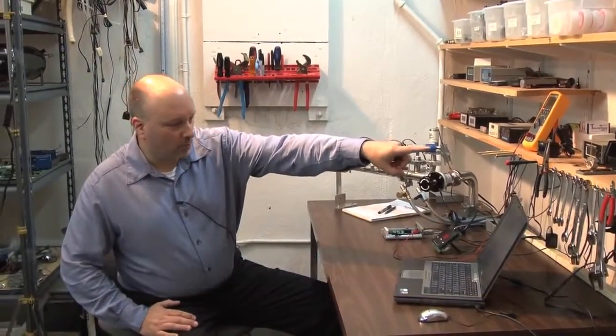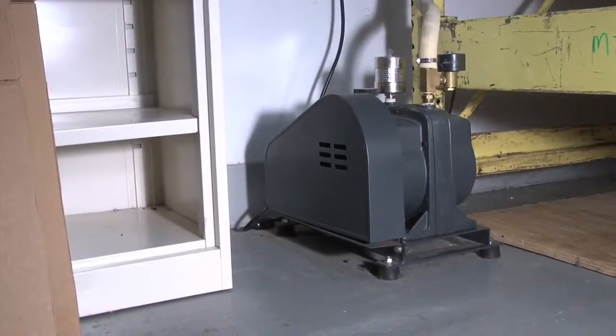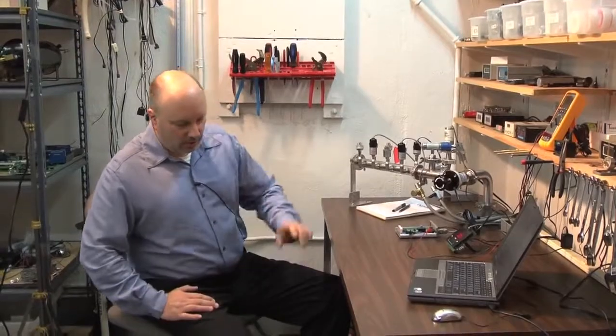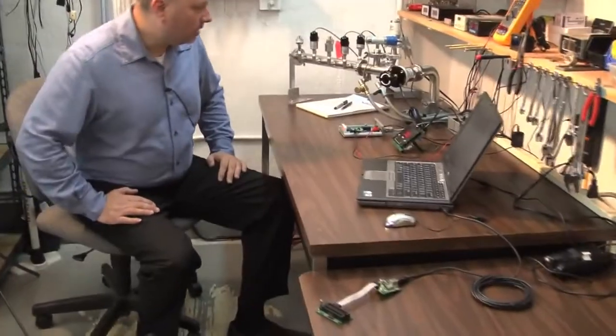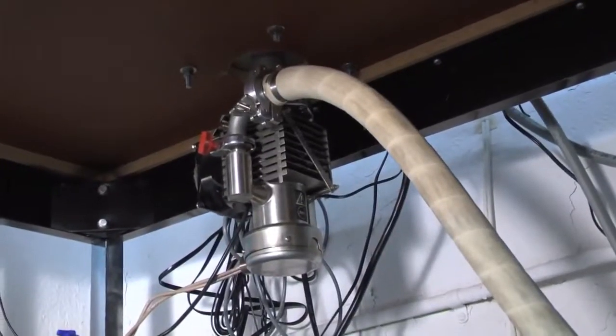In order to calibrate our instruments it takes three vacuum pumps. The first vacuum pump outside behind the wall is a rotary driven oil-based pump. Our second pump is a small rough vacuum oil-based pump. Our third pump is a high vacuum diffusion pump mounted underneath the table.